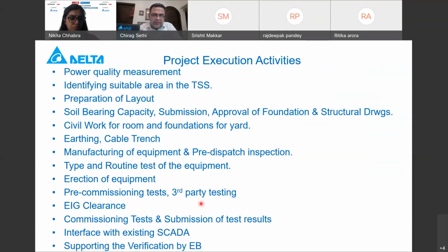Pre-commissioning, then any third-party test, seeking EIG clearance, then final commissioning after charging with 25 kV, and thereafter, as a last step, integrating with the SCADA as well as supporting the verification by the electricity board.